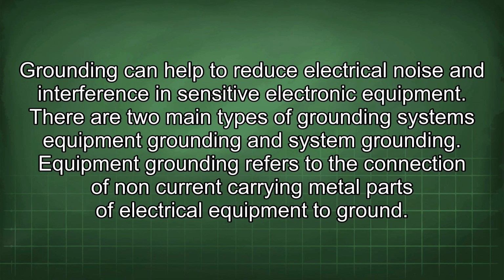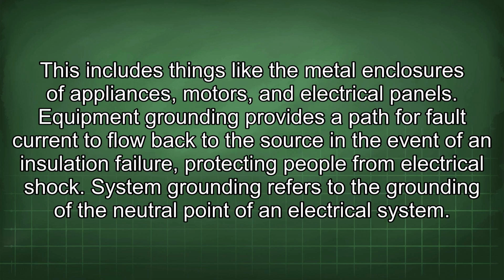There are two main types of grounding systems: equipment grounding and system grounding. Equipment grounding refers to the connection of non-current carrying metal parts of electrical equipment to ground. This includes things like the metal enclosures of appliances, motors, and electrical panels. Equipment grounding provides a path for fault current to flow back to the source in the event of an insulation failure, protecting people from electrical shock.